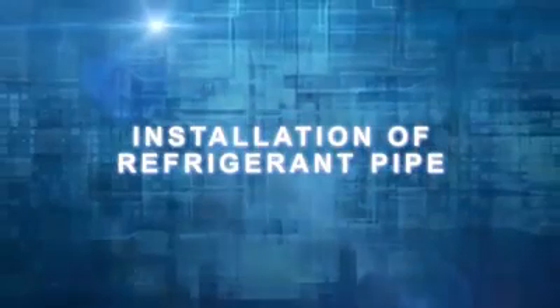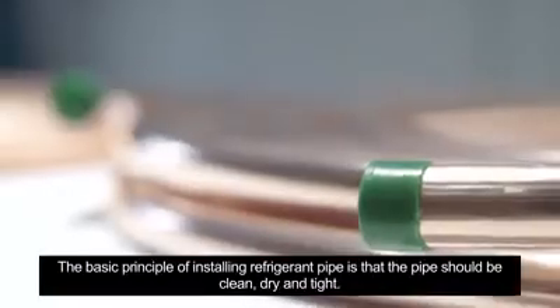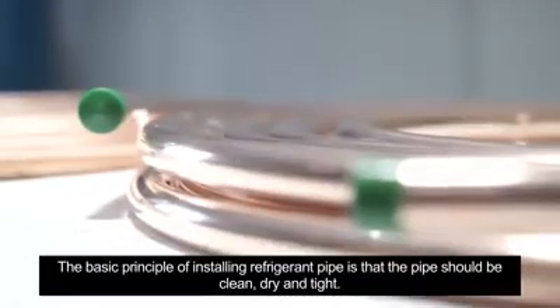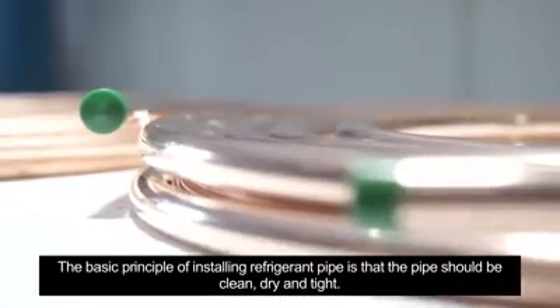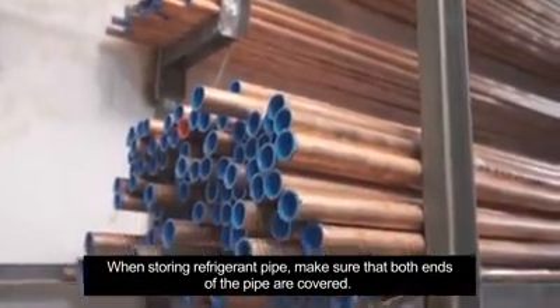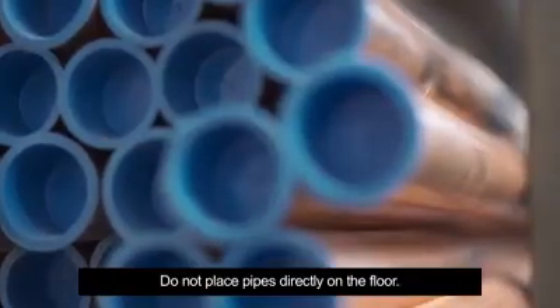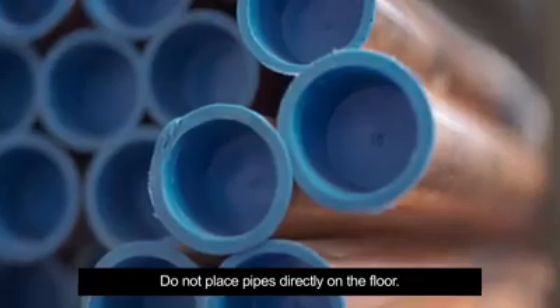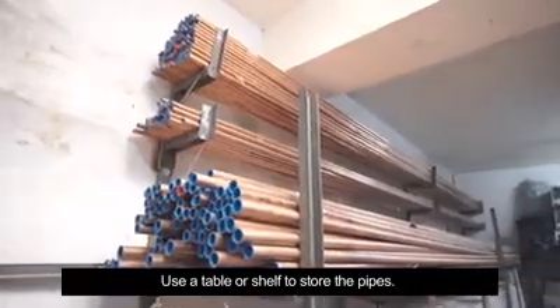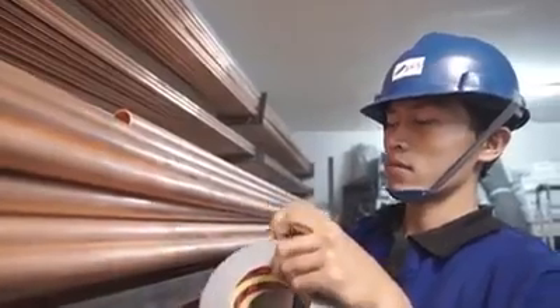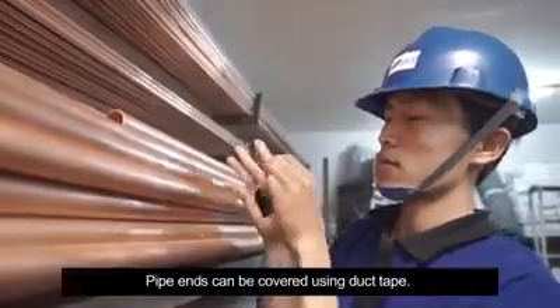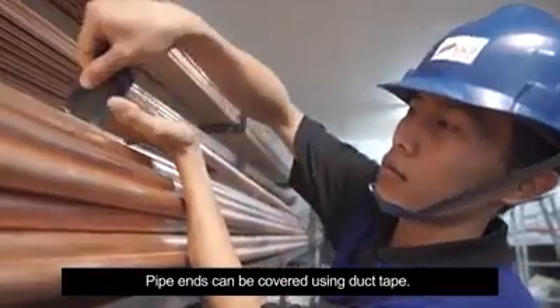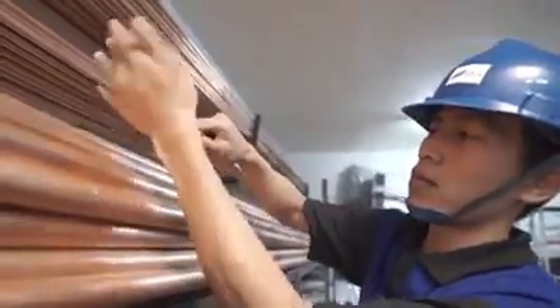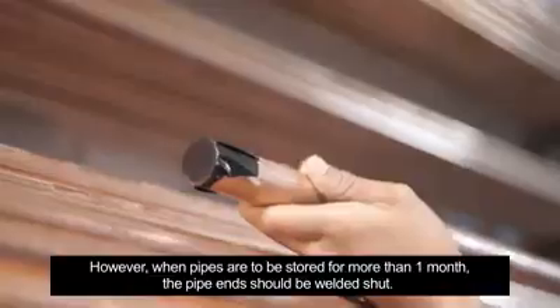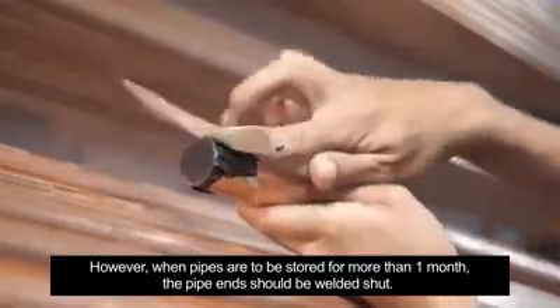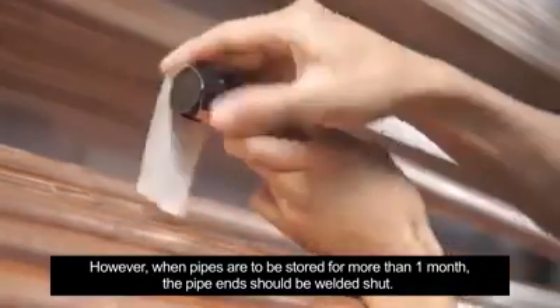Installation of refrigerant pipe. The basic principle of installing refrigerant pipe is that the pipe should be clean, dry and tight. When storing refrigerant pipe, make sure that both ends of the pipe are covered. Do not place pipes directly on the floor. Use a table or shelf to store the pipes. Pipe ends can be covered using duct tape. However, when pipes are to be stored for more than 1 month, the pipe ends should be welded shut.